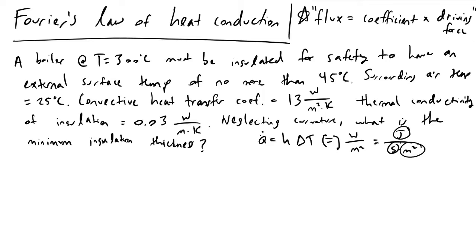Working through the example: we have a boiler running at 300°C and we want to insulate it so that a worker touching the surface of the insulation feels no more than 45°C. We're told the ambient air temperature is 25°C, the convective heat transfer coefficient is 13 W/m²·K, and the thermal conductivity of the insulation is 0.03 W/m·K. Neglecting curvature, we want to find the required thickness of insulation.